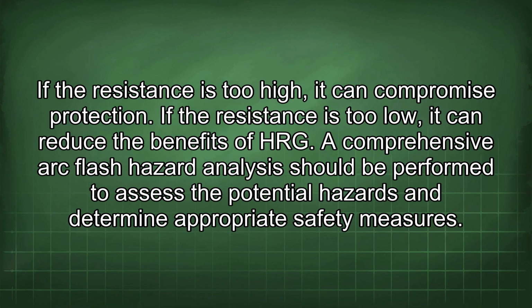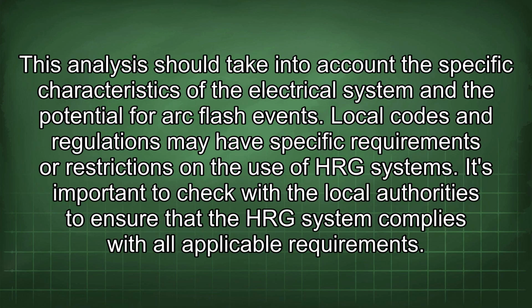A comprehensive arc flash hazard analysis should be performed to assess the potential hazards and determine appropriate safety measures. This analysis should take into account the specific characteristics of the electrical system and the potential for arc flash events. Local codes and regulations may have specific requirements or restrictions on the use of HRG systems. It's important to check with the local authorities to ensure that the HRG system complies with all applicable requirements.